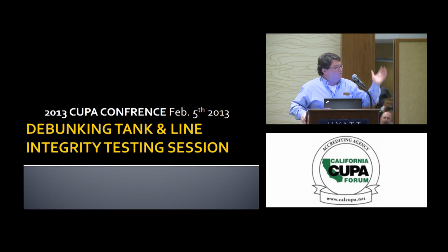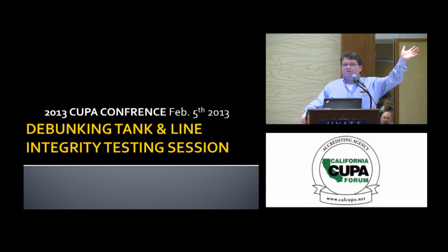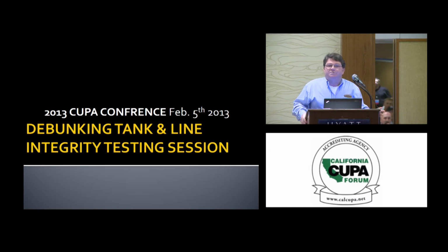Water entry. Do we ever have water entry in California? You guys got phase separation anywhere? Does that happen in California? A couple hands raised, certainly your single wall guys. Troubleshooting. This is the magic of tank testing. Because quite frankly, if the tank's buried in water, you got a Veeder-Root pumping out 0.2 every month, everything looks great, you're just blessing that tank. What do you do when there's a problem? That's where tank testing is needed.